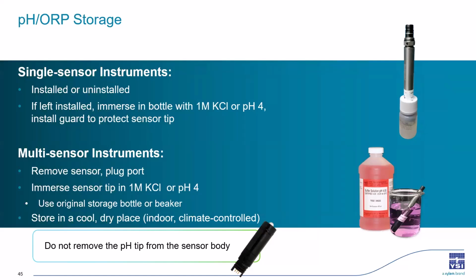If you have a lab or an office where you have a cabinet to put it in, that's great. And this is going to go for all of your sensors. They should be stored indoors in a climate-controlled area. If your sensor does have a removable tip, don't remove it before storage. It could potentially destroy the O-rings on the modules, and you won't be able to put the tip back on. You can replace it if you need to when you take it back out of storage, and keeping it on will also just help protect the sensor internals.